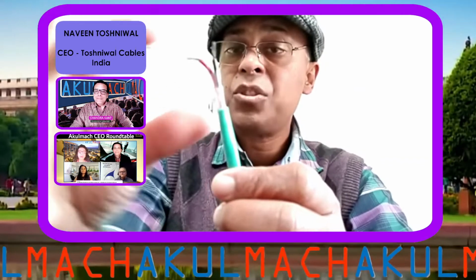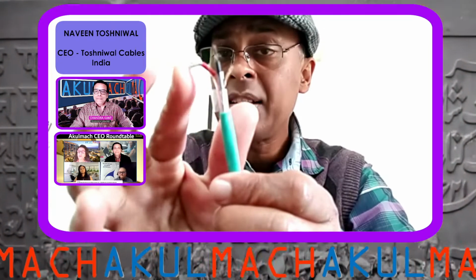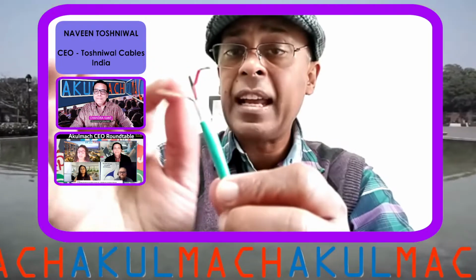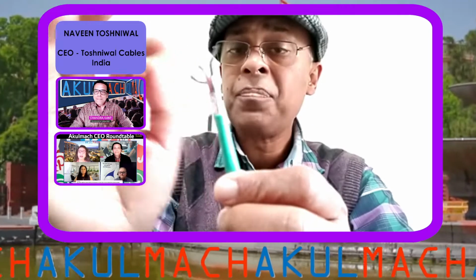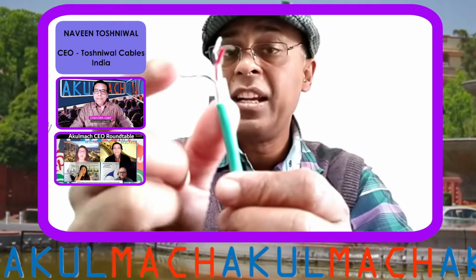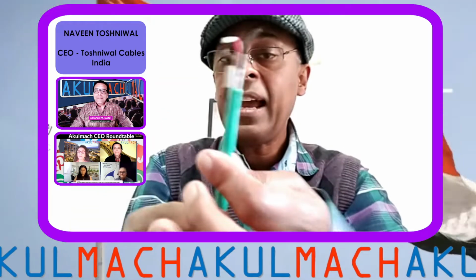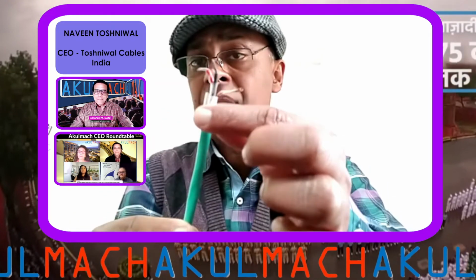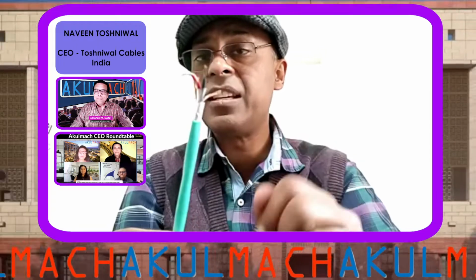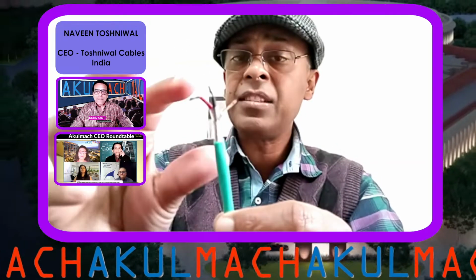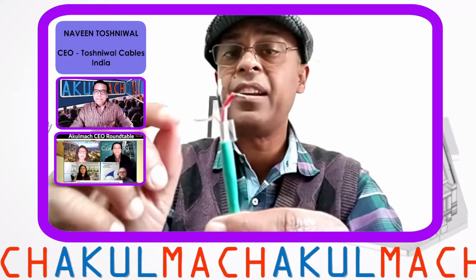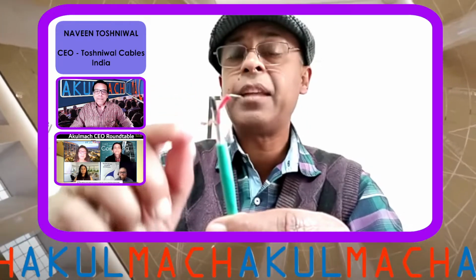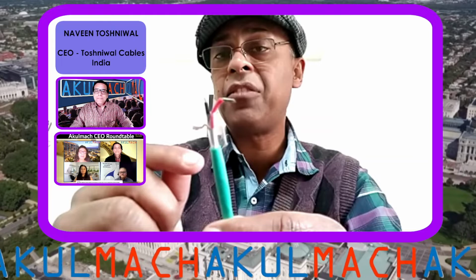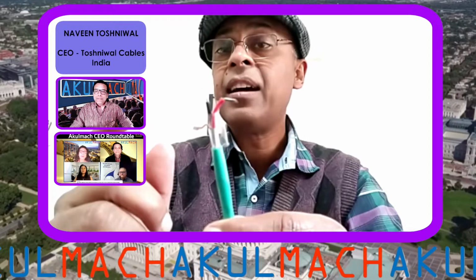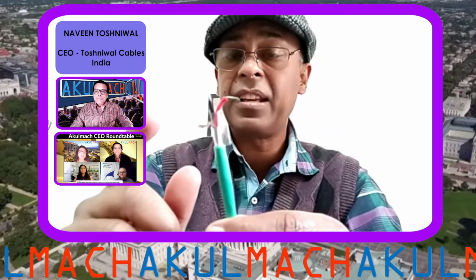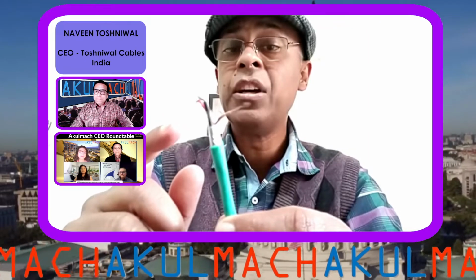So this is actually a multi-strand compensating cable which has an insulation of PVC on each core, and then we have this electrostatic shielding, as I explained, for earthing, and then we have the outer covering, which is the final PVC covering. Now again, this insulation can be of any material. It can be PVC, polyethylene, Teflon or rubber. Again, it depends on the particular site application and where the client wants to use this cable.